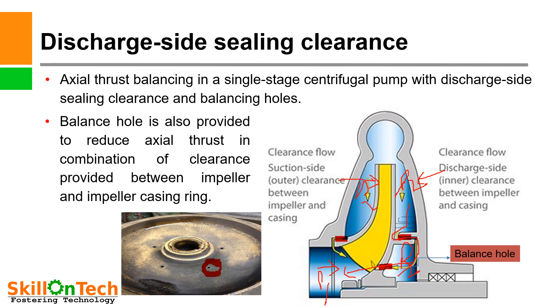Suction side wear rings are designed to limit the flow of pumpage from the higher pressure discharge side of the impeller to the lower pressure suction side. Excessive clearance of these rings can result in increased flow across the suction side and a volumetric loss of efficiency. Rear wear rings, when present, work in tandem with balance holes that pass through the suction eye to lower the suction side pressure behind the impeller and inside the rear wear ring, limiting the axial thrust force. This discharge side inner clearance between impeller and casing, provided in tandem with the balance hole, is one important method to balance axial thrust in a single stage centrifugal pump with single suction.